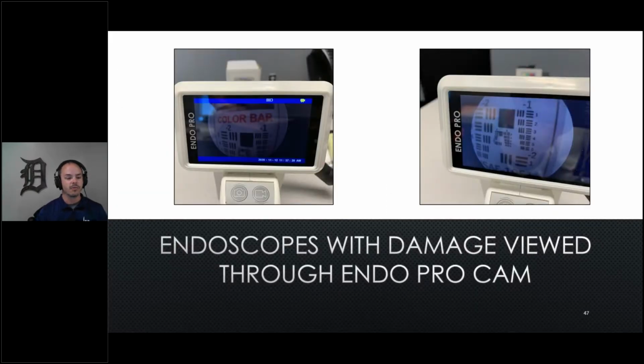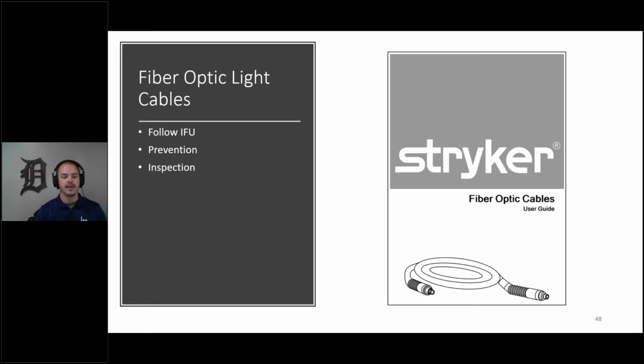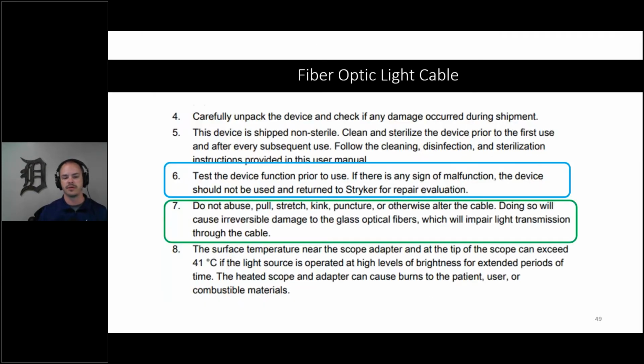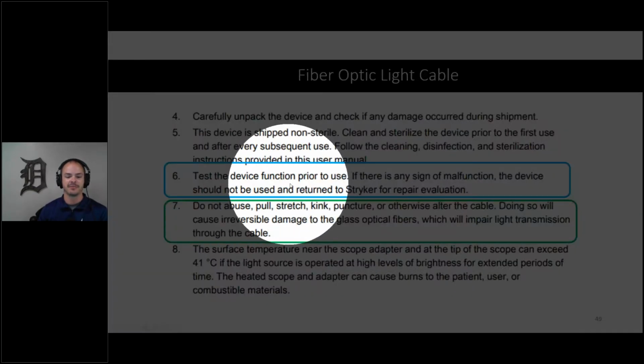So what about the light cables? Those are an important part as well. Let's take a look into the IFU of a common fiber optic light cable, because this is an important quality control aspect. It specifically says to test the device function prior to use. If there's a sign of malfunction, the device should not be used and should be returned for repair and evaluation.